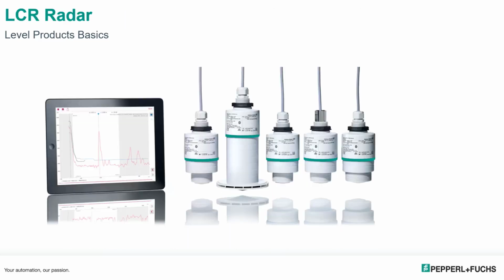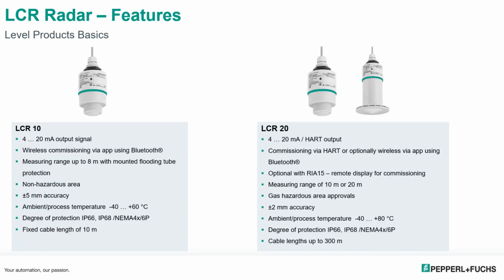Another type of radar probe we offer is the freestanding LCR radar. Unlike the guided wave radar where you send the signal down the rod and it reflects off of the medium surface, the freestanding is almost like an ultrasonic, except it has a much higher frequency to send and receive off the medium. The LCR-10 is offered in a 4 to 20 milliamp output. You can commission it through the Bluetooth because these are wireless. It's only available with non-hazardous area applications, plus or minus 5 millimeter accuracy, minus 40 to plus 60 degrees C ambient and process temperature range.